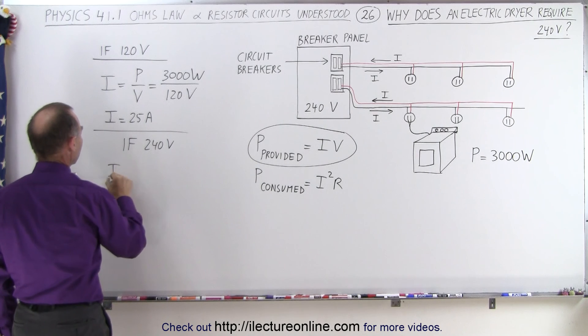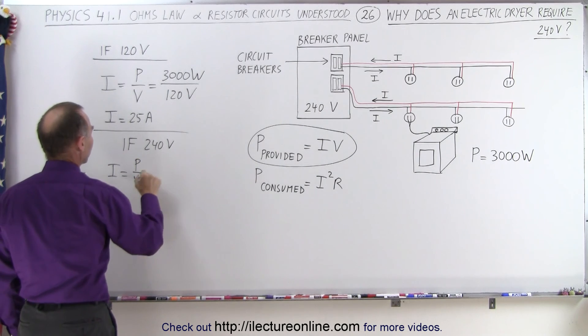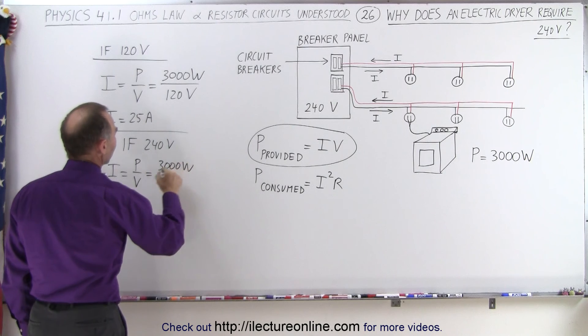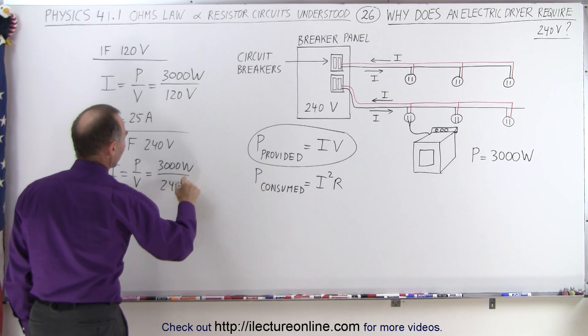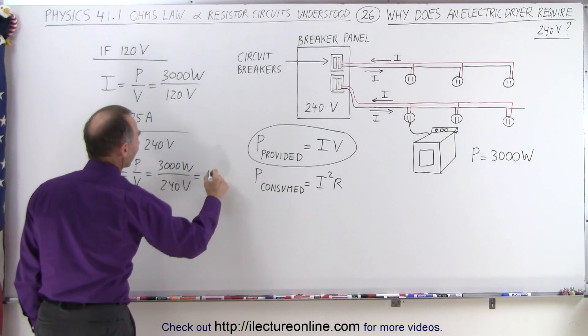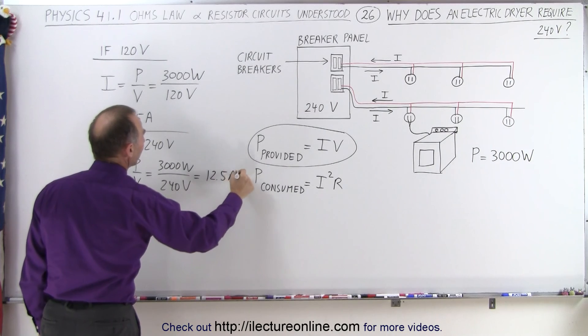Well, if we now use 240 volts, notice that will reduce the current required to run the dryer. I being equal to the power divided by the voltage, which is 3000 watts divided by 240 volts. Well, double the voltage means half the current - you'd only need 12.5 amps.